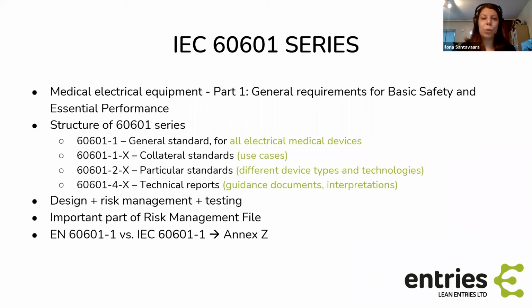Then there are also technical reports. These are guidance documents, interpretations. I'm not very familiar with most of these. I think I haven't applied any of them in practice, but they're definitely helpful in some situations. And the main principles of the standard series are that you have to apply these principles in device design. You have to do risk management and include them in the risk management file. And then you also need to do some testing ultimately. But it cannot be emphasized enough how important a part of the risk management file this is. So you cannot just send your device for testing and get the report back. That won't be enough.